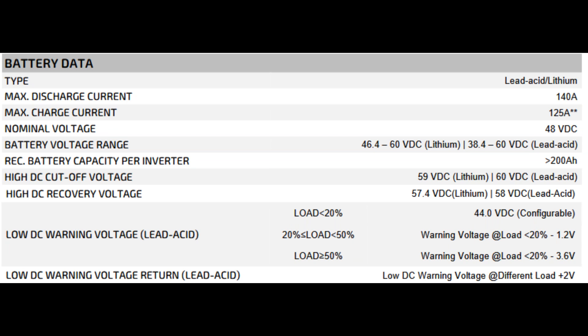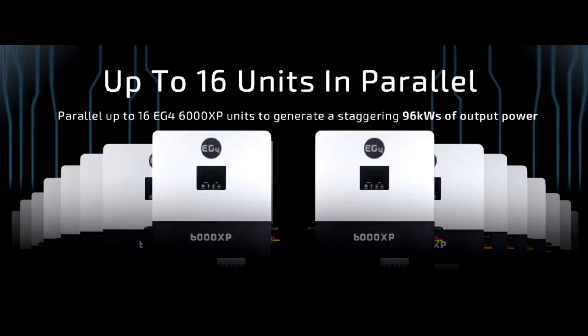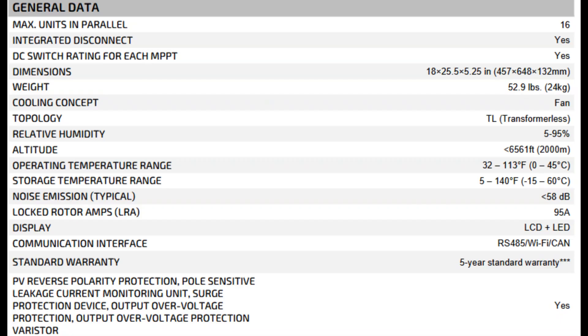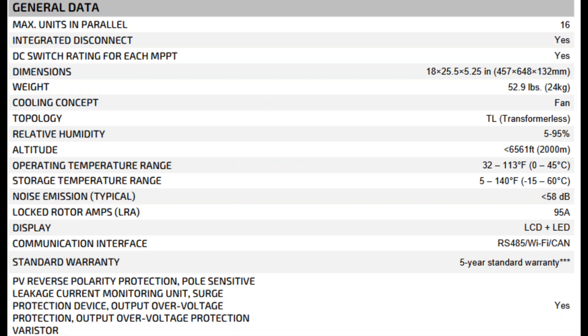The high DC cutoff and low DC warning settings protect your batteries from damage. The inverter can be configured to alert you or shut down to prevent battery over-discharge or overcharge. You can build some serious power plants by paralleling up to 16 of these. That's 96 kilowatts of potential output. It also mentions dimensions, weight, cooling, and operating temperature range. Just make sure you keep it within 32 to 113 degrees Fahrenheit for best performance.